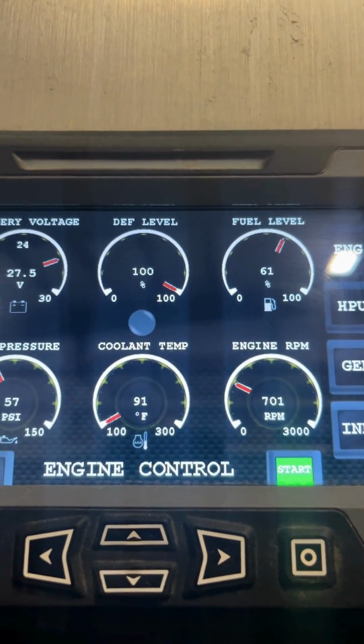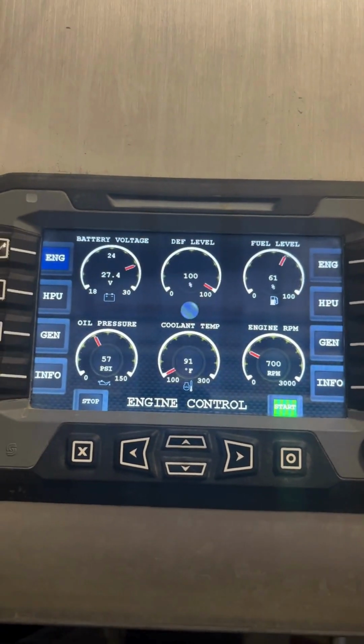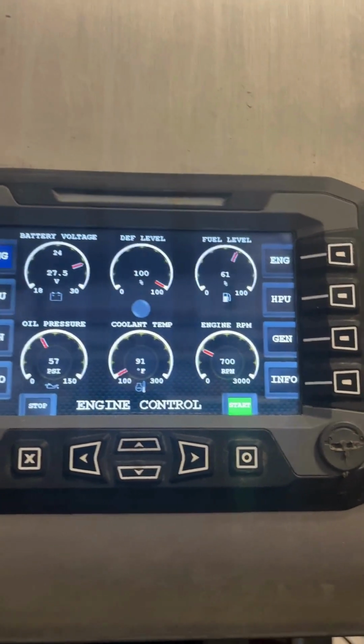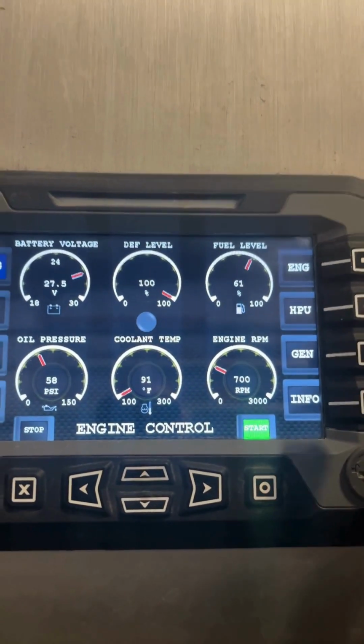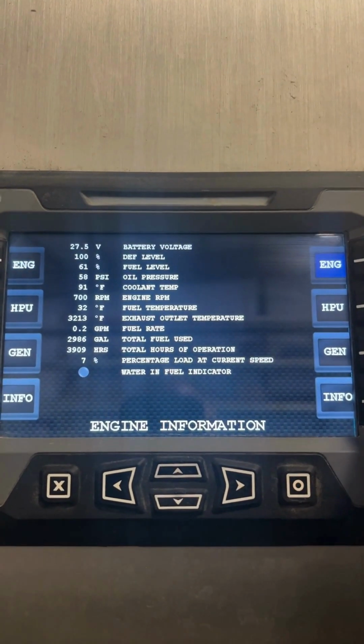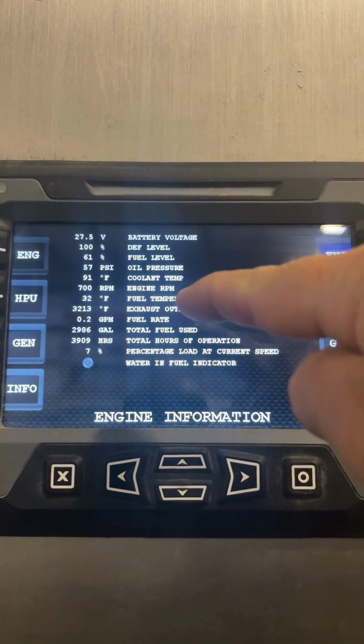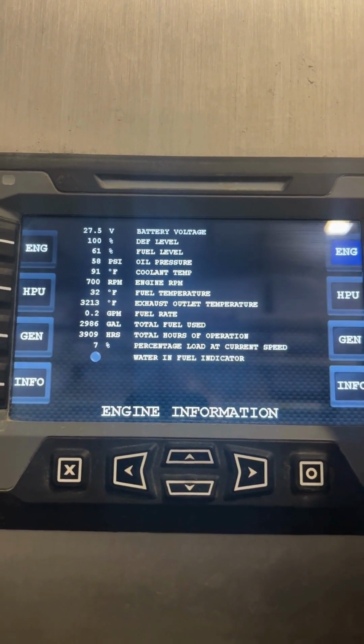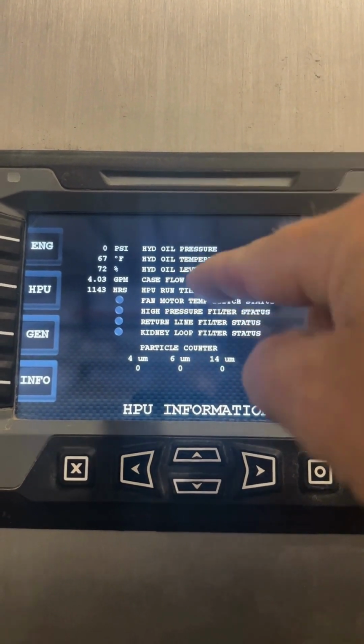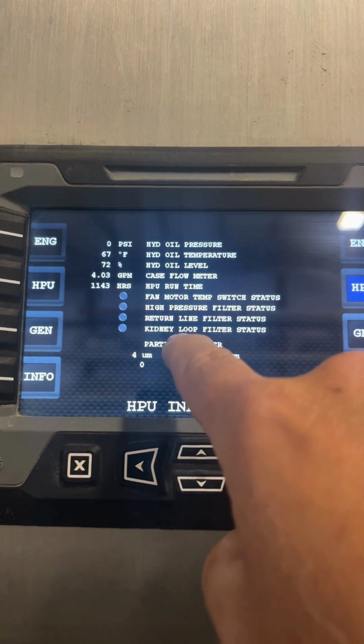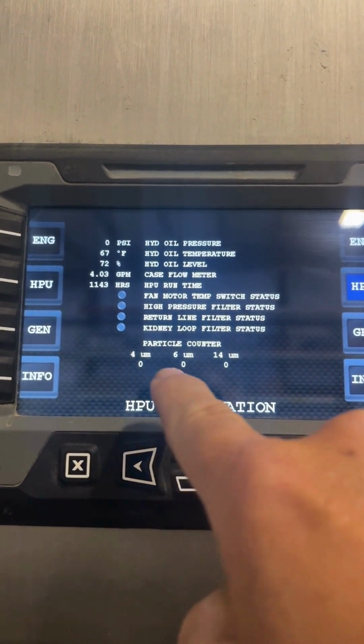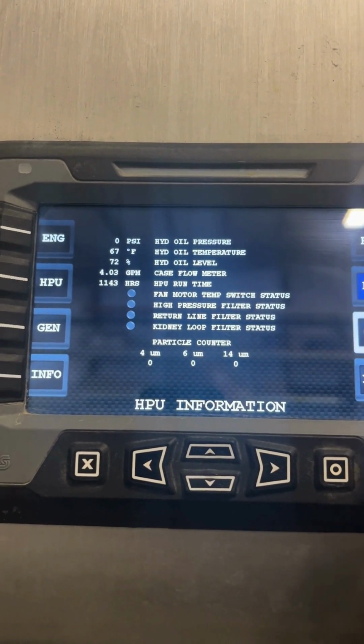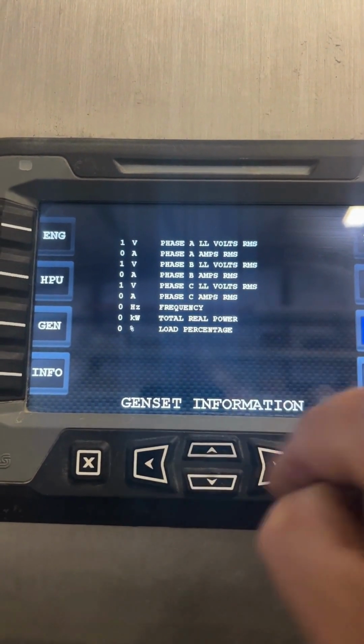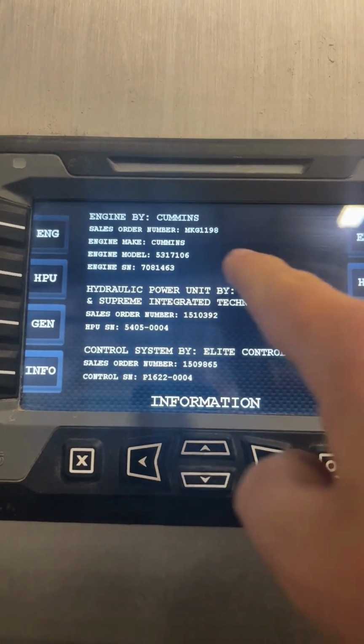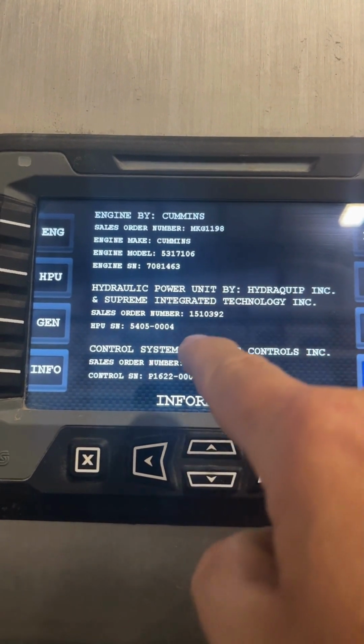The engines will stay at about 700 RPM until the coolant temperature gets to about 100 degrees, and only then enable the unit to go to full. The screens on the right offer the maintenance departments a lot more data on the various subsystems, should more in-depth analysis of the system be required. Again, we can see the particle counters and exactly what's going on the voltage side. Then on the info screen, we can see all the work order numbers for this specific unit.